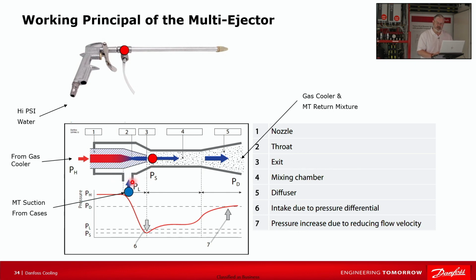This is the suction return from medium temp. It comes in here and joins the gas cooler mass flow, which is not unlike the soap solution from the tube that drops out of your pressure washer wand. And then the two mix together through the mixing chamber here and then exit through the diffuser. Very similar to our pressure washer wand. They mix together here and then exit as a soap and water mixture. So our soap and water mixture for the pressure washer example is our gas cooler and medium temp return gas mixture.